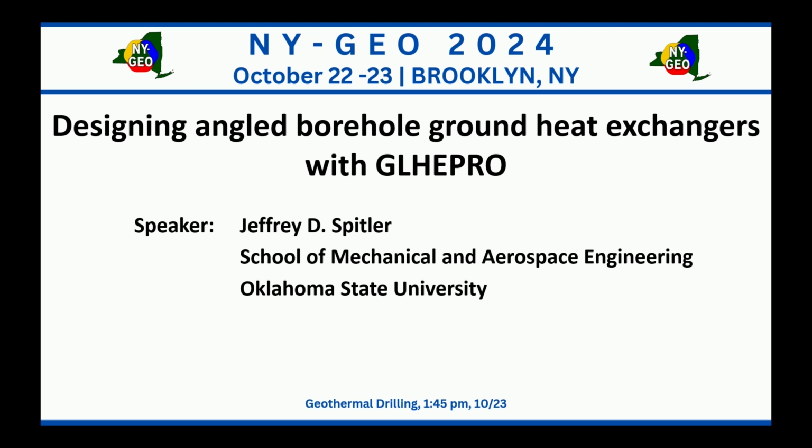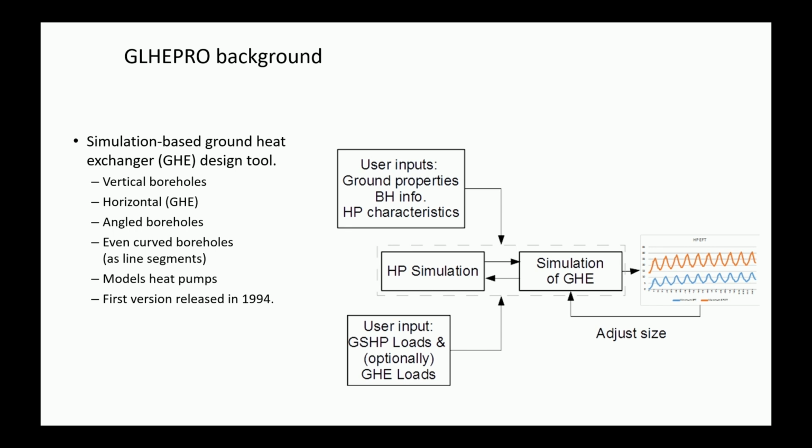Okay, so I'm going to speak a little bit about using GLHE Pro to design angled borehole ground heat exchangers. GLHE Pro is a simulation-based ground heat exchanger design tool. It can do vertical boreholes, horizontal ground heat exchangers, angled boreholes. It could even do curved boreholes that you might get if you were using a horizontal drilling rig and you went down 15 feet and then came out somewhere and pulled the loop back through as line segments. It models heat pumps, and the first version was released 30 years ago.